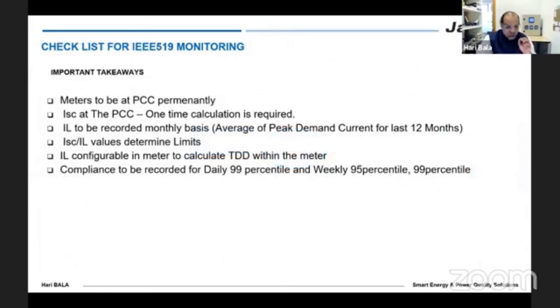So I will give a short checklist of what is required for IEEE 519 monitoring for the consumers. The meters have to be permanently on the PCC. The ISC value should be calculated. IL to be recorded on a monthly basis. ISC by IL value should be determined. And this IL should be configurable in the meter on a monthly basis so that the TDD is calculated accordingly.